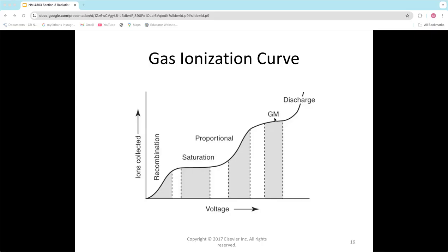In the GM range, your voltage gets really, really high. When the radiation strikes and you get the electron and the ion pair, you start to get really high velocity actions towards the cathode and the anode. They just start traveling at a high speed. I'm going to go to the next slide because we're going to look at what happens. This GM reaction is different from what happens in the saturation range. This is what makes your meters different: an ionization meter that you use to get a rate and a reading, versus a GM, which is used to detect small amounts of radiation, on and off. I'll get more detail on that, but let's go to the next slide.